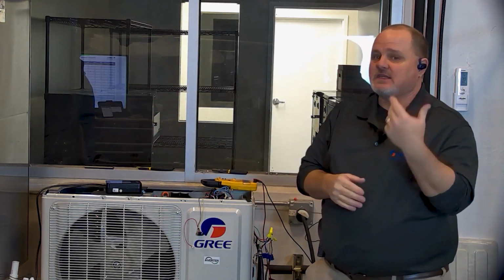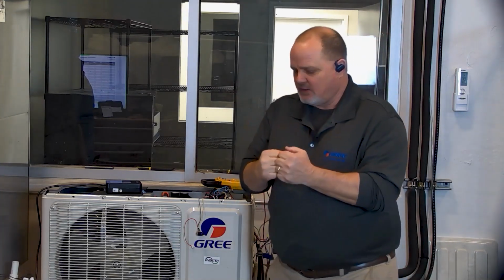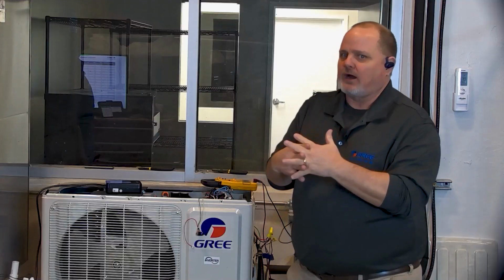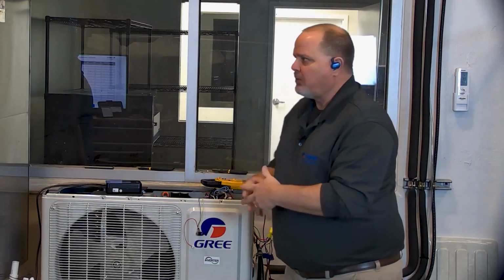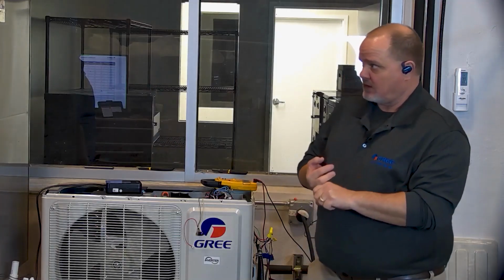The 300 volt wire versus the 600 volt wire: that means the insulation class is on the wire, but the individual wires inside do not have that 600 volt rating, which means you have more of a chance of that voltage bleed between the wires. Again, you may never pick it up with an ohm meter. That's why they specify 600 volt 14-4 wire, because it's flexible and it has a high voltage rating for the class of the insulation. It still doesn't mean you couldn't get a bad wire. What it means is you're going to have less chance of having a bad wire because you used 14-4 600 volt stranded wire.